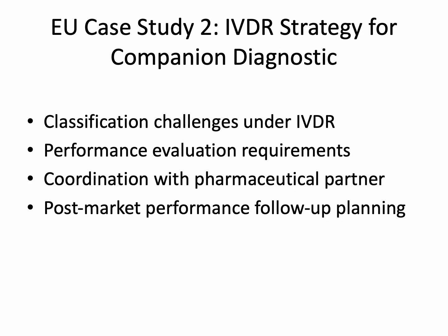This study explores the regulatory pathway for a companion diagnostic under the EU IVDR. Classification challenges arose due to novel indications and integration with a pharmaceutical therapy. Performance evaluation requirements included analytical and clinical performance data, risk assessment, and interoperability considerations.